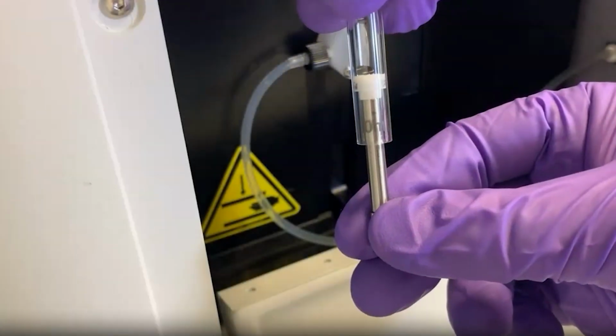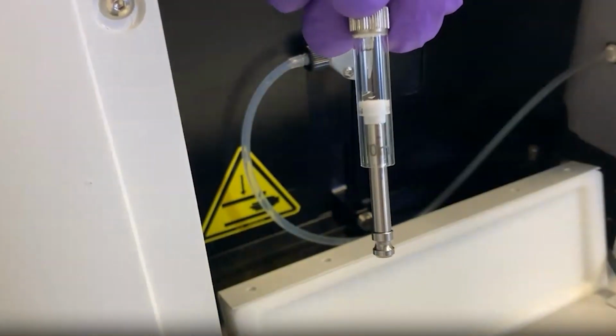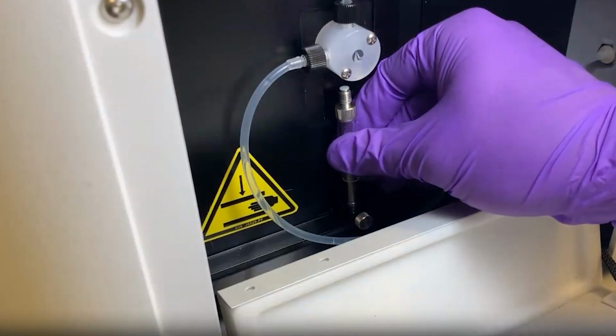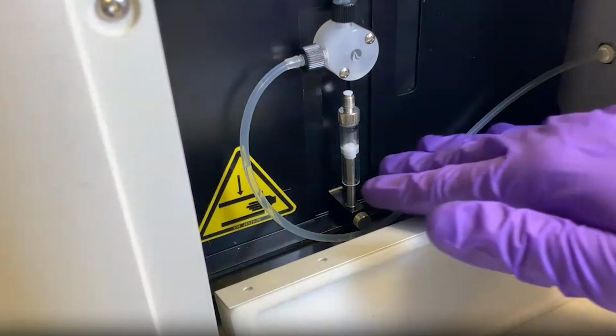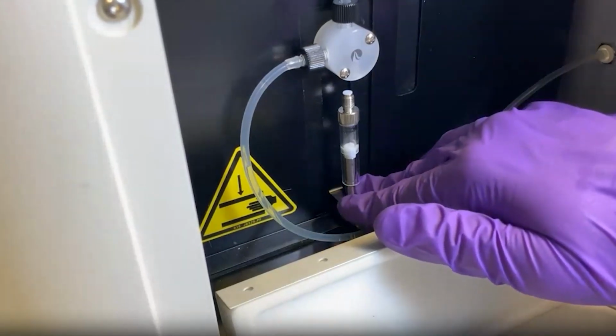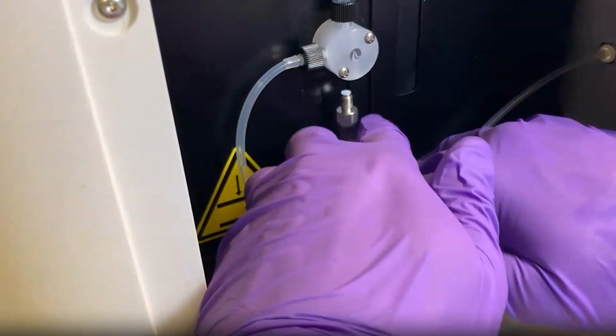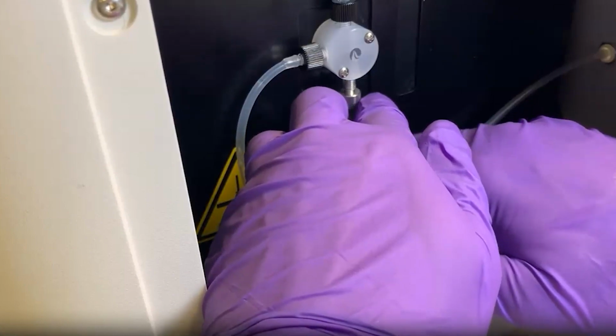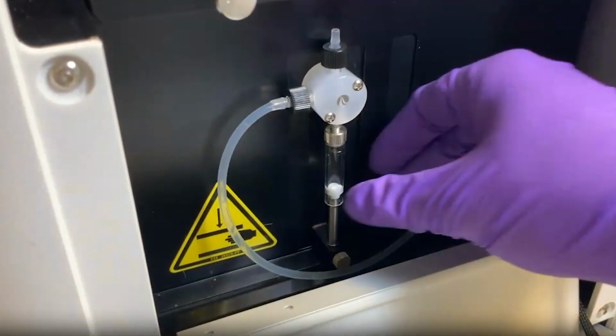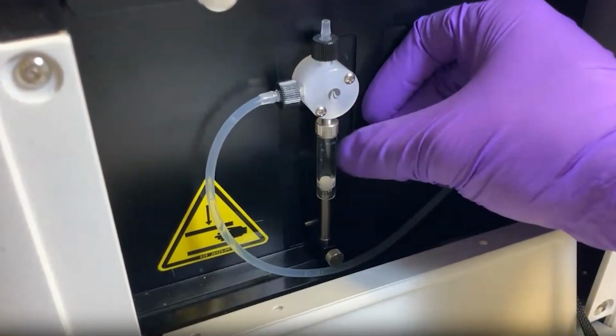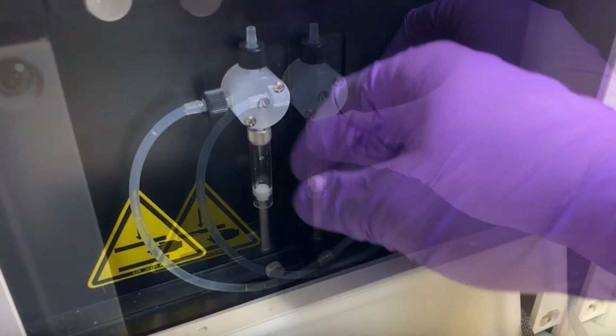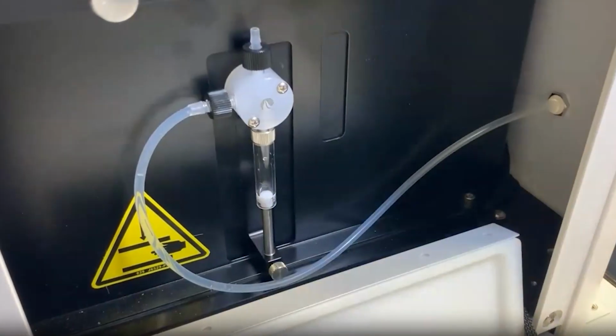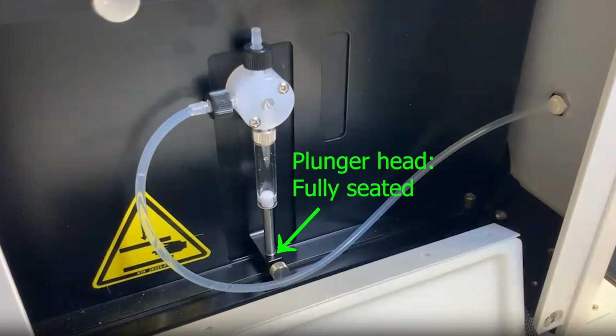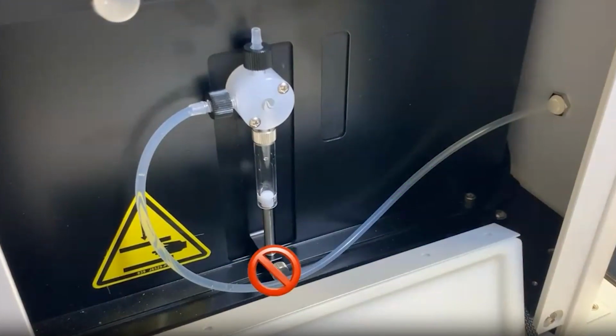Another way to install the pump syringe is to first pull the plunger arm out of the barrel about halfway, and then seat the plunger arm head directly into the pump arm socket. With one hand securing the plunger arm in place, use the other hand to raise the syringe barrel and securely thread the syringe barrel screw into the pump manifold. Remember to check that the plunger arm head is fully seated in the pump arm socket. Do not tighten the plunger lock screw yet.